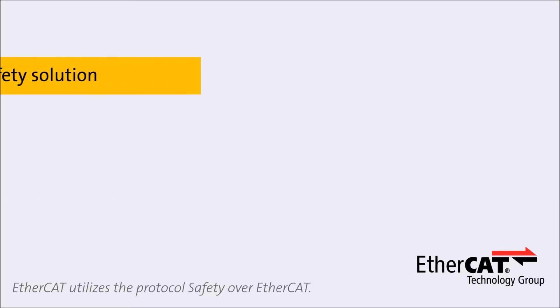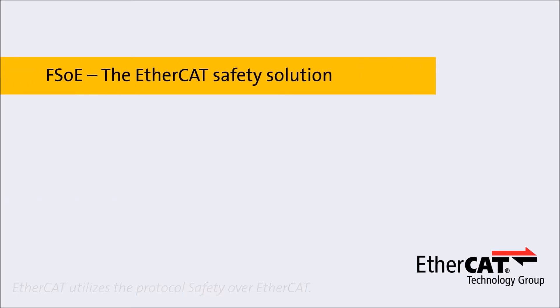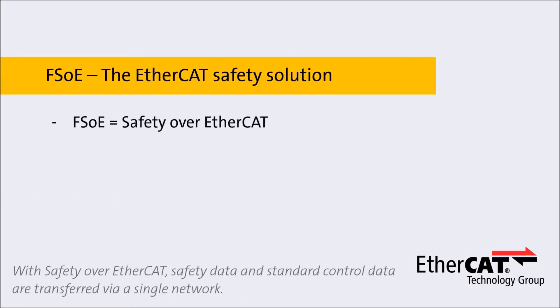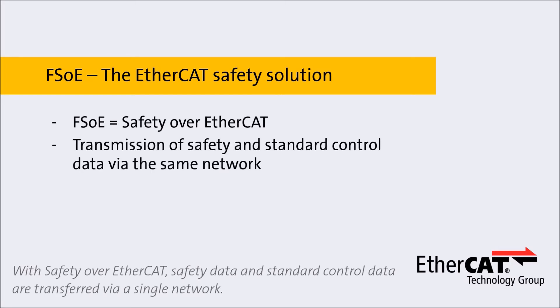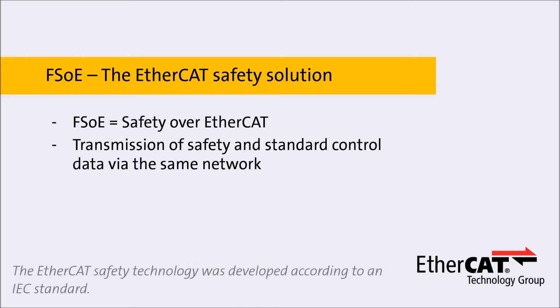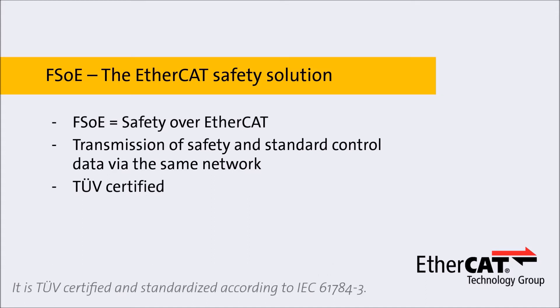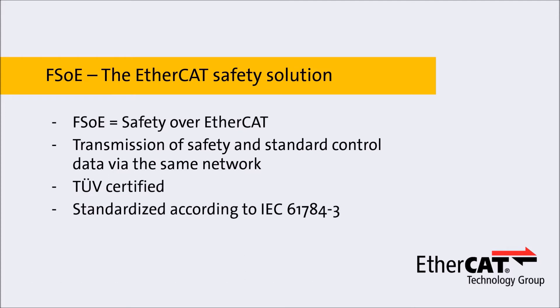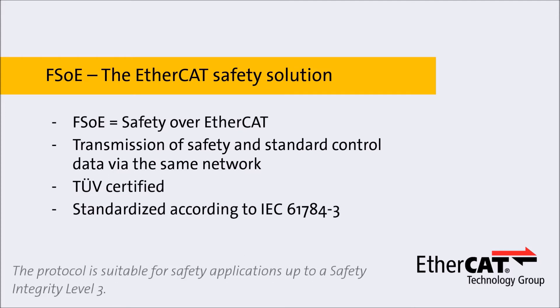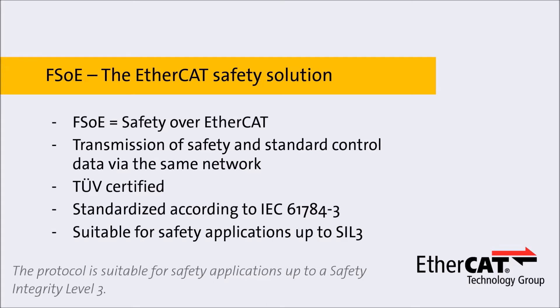EtherCAT utilizes the protocol Safety over EtherCAT. With Safety over EtherCAT, safety data and standard control data are transferred via one single network. The EtherCAT safety technology was developed according to an IEC standard. It is TUV certified and standardized according to IEC 61784-3. The protocol is suitable for safety applications up to safety integrity level 3.